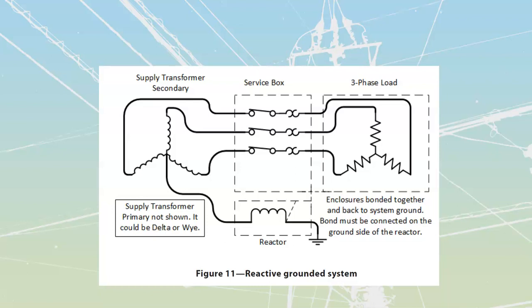Reactance grounding isn't as good as resistance grounding, but it's easier to build a reactor than a resistor. We control the currents, but we're not going to get as good of a result. We're usually able to knock it down to maybe 50 to 70% of what the unrestricted value of current would be.